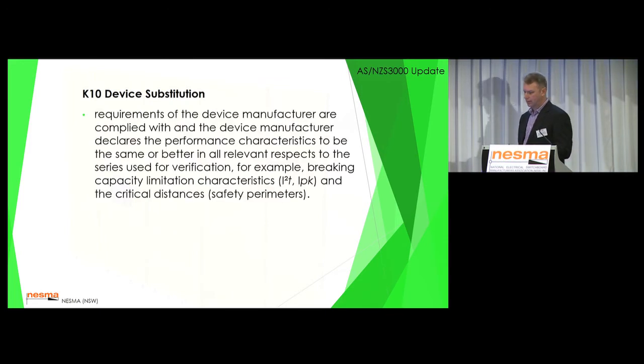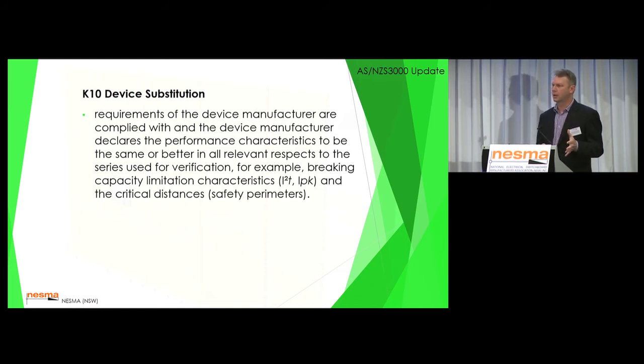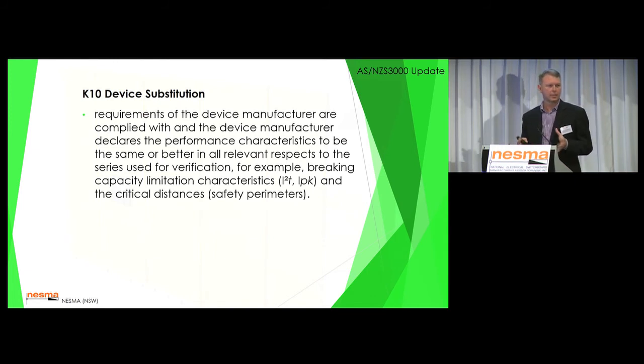And the requirements of the device manufacturer are complied with, and the device manufacturer declares the performance characteristics to be the same or better in all relevant aspects to the series used for verification. So if we're talking about device substitution from one range of a supplier to a newer range that's coming out, then you're likely to get that device manufacturer provide you the data that says that they are as good or better than the previous range you tested. Device substitution under that situation is quite simple.